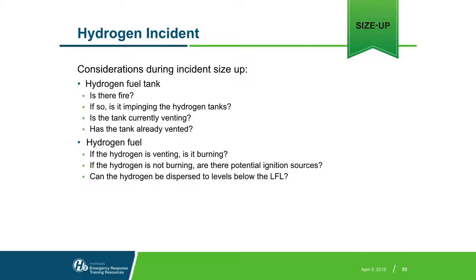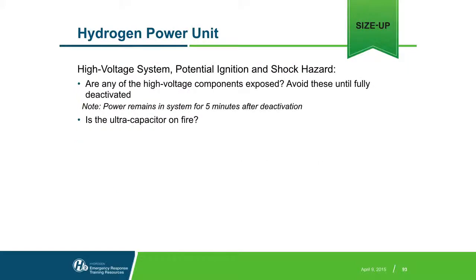When we were here for training with the fuel cell flame prop, if any of you recall, one of the tactics was to employ a 45-degree angle fog spray to divert a hydrogen flame or venting hydrogen. And I would say that that could be a tactic in this case, if need be, to help disperse the hydrogen that's venting. There is high voltage on this system because we have the fuel cells, we have the ultracapacitors and the inverter. And again, those lines will be marked with orange to indicate anything over 60 volts.